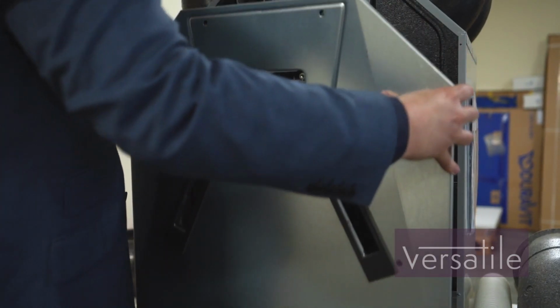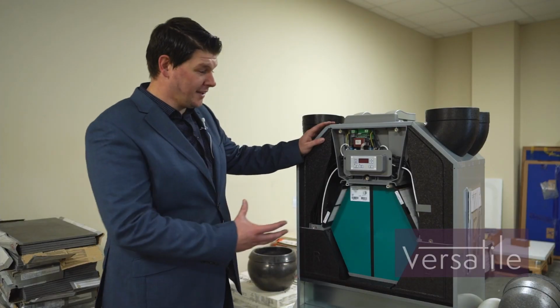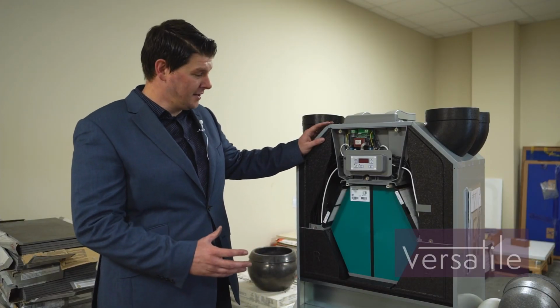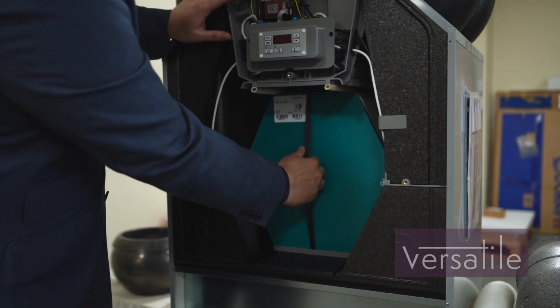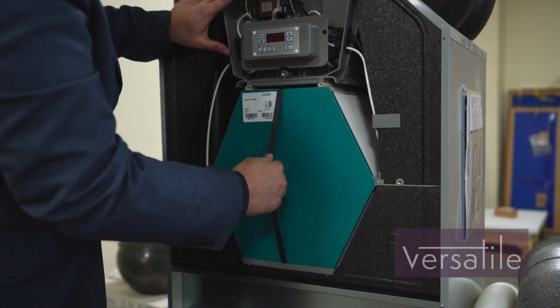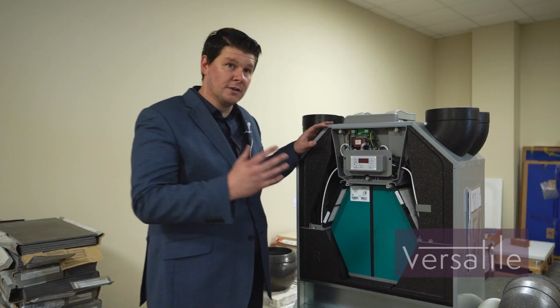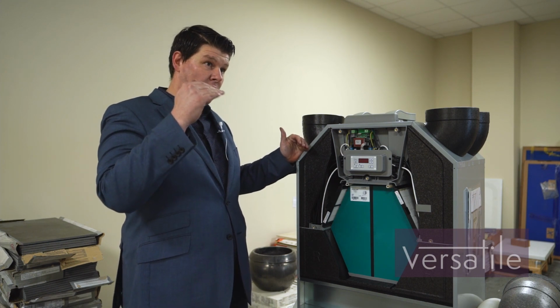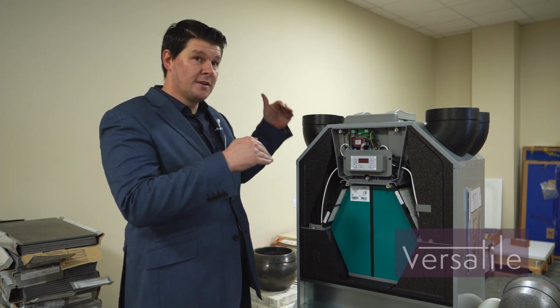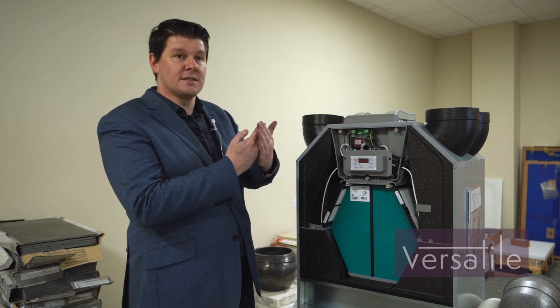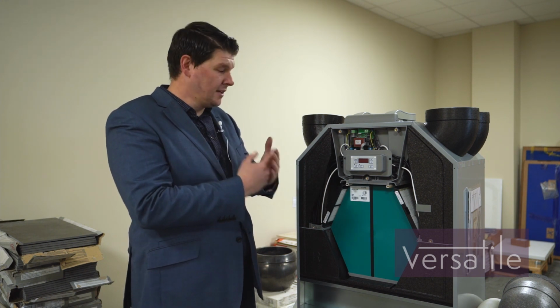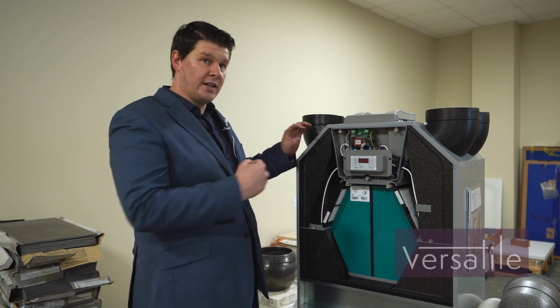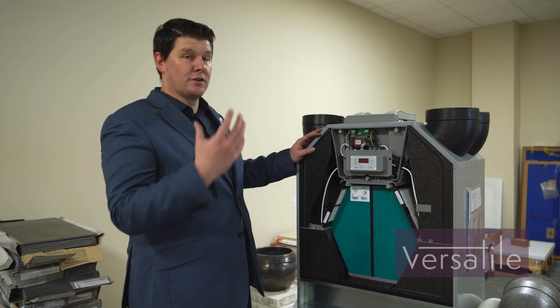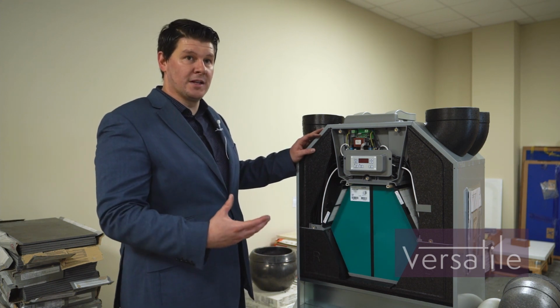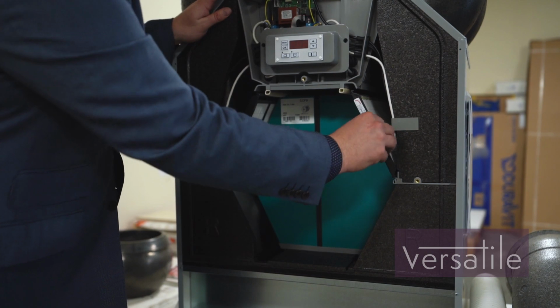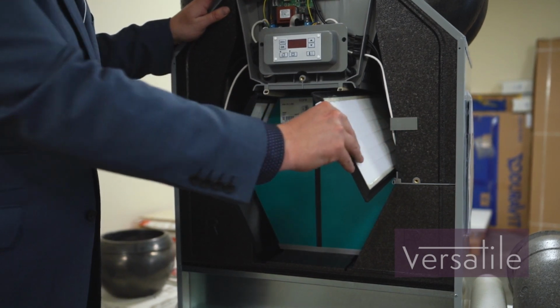Okay, so we've opened up the hood of the unit here now, so we're looking at the internal heart of what's happening inside. The main thing to note is the heat exchanger. So we've got this hexagon-shaped unit in here that's allowing us to pass the flow of cold, fresh air coming in from outside and move it past the warm, stale air that's leaving. So we can exchange the heat, bring the heat into the supply side and recover that energy, so we're making the building more efficient.